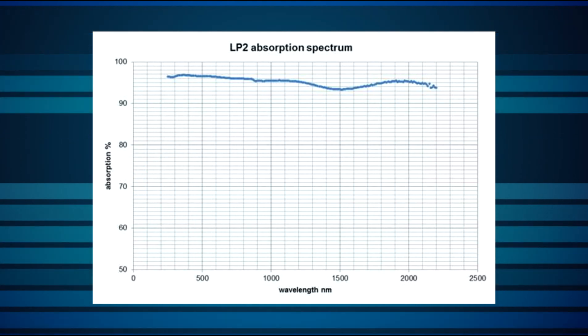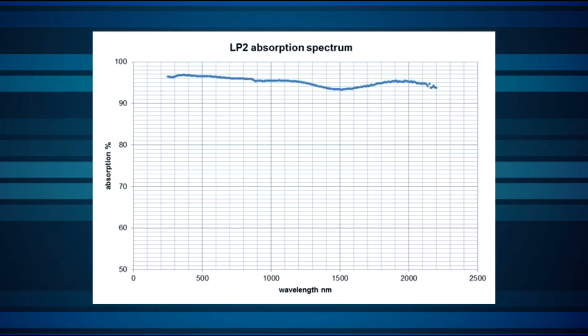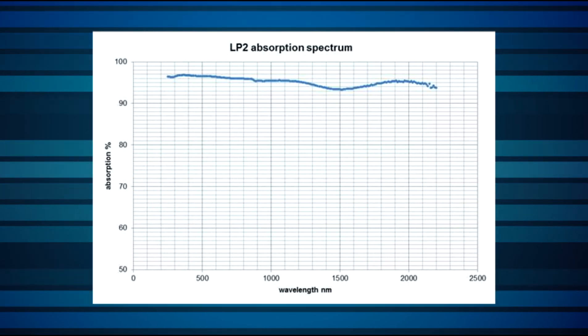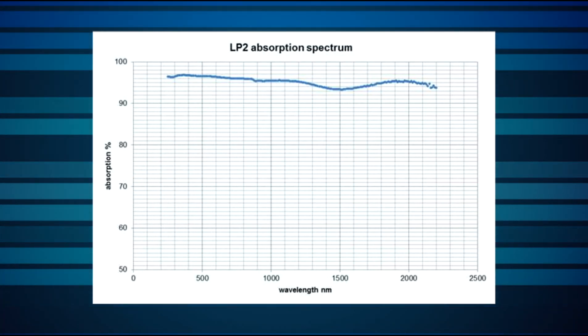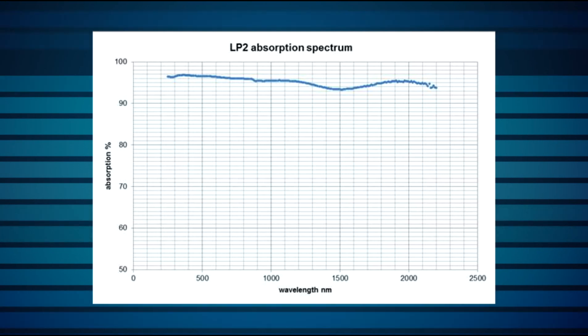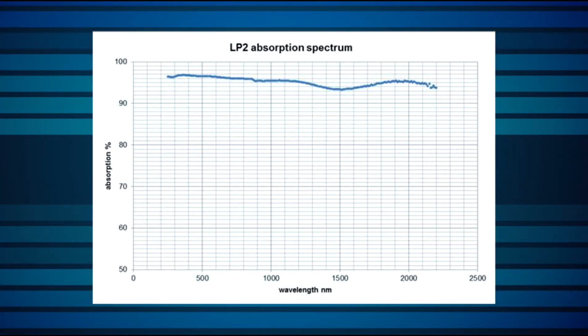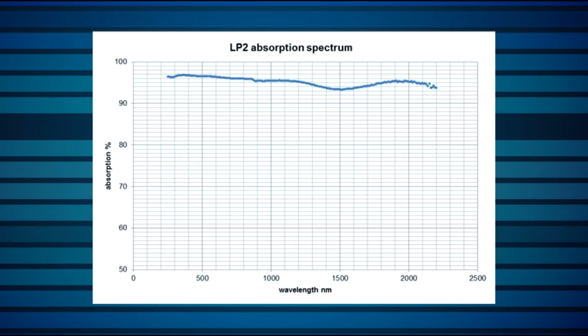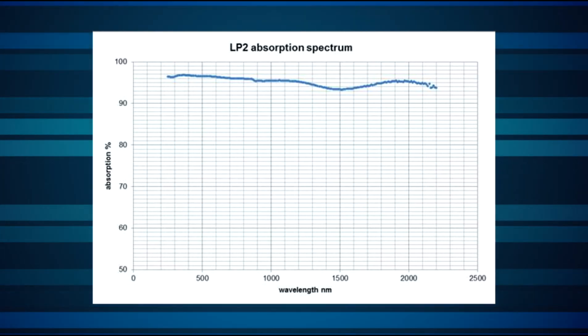2. Broad spectrum. The L40-150A IPL uses Ophir's LP-2 absorber, which is very spectrally flat. This ensures maximum accuracy of your measurements, regardless of differences among flash lamps, and regardless of whatever spectral filtering is used in any given application.